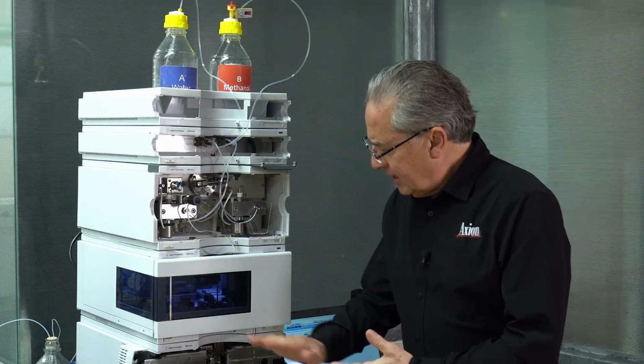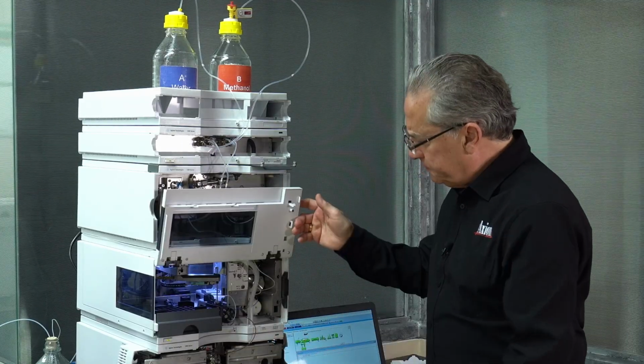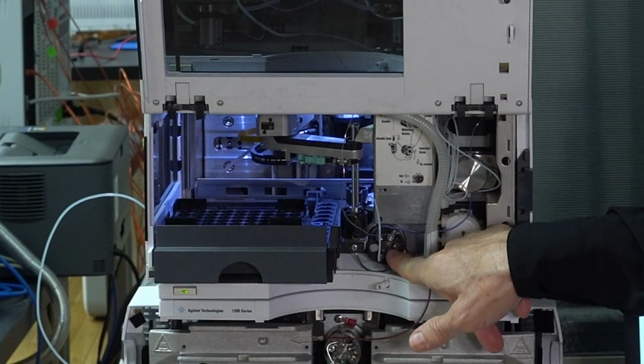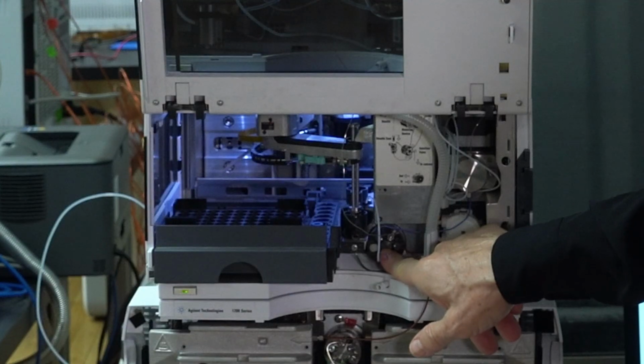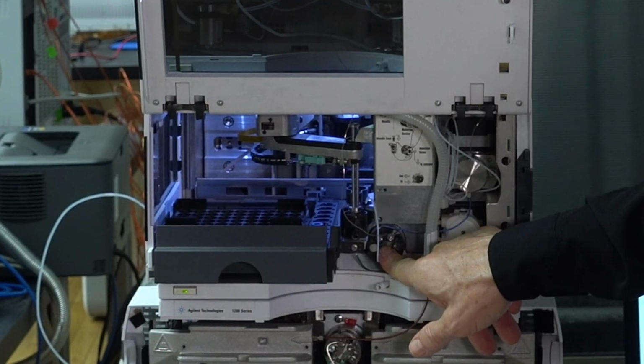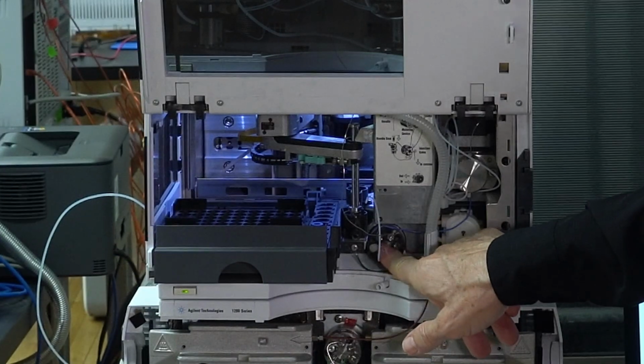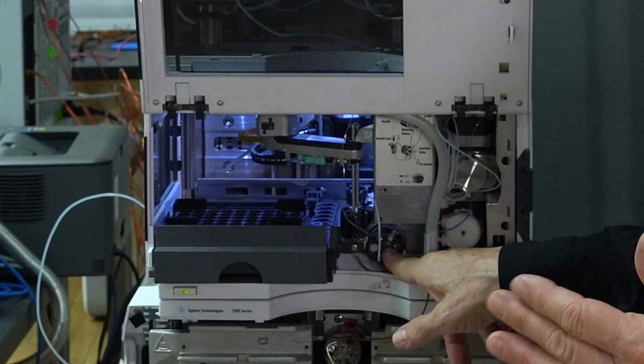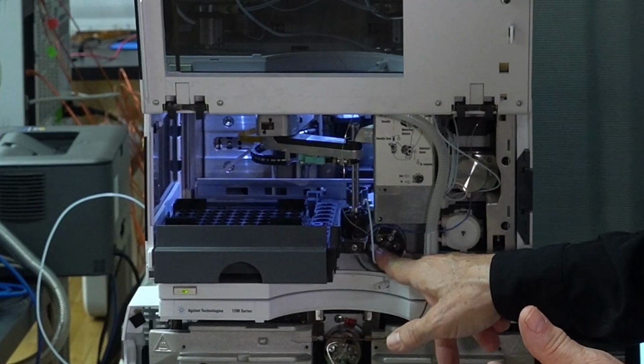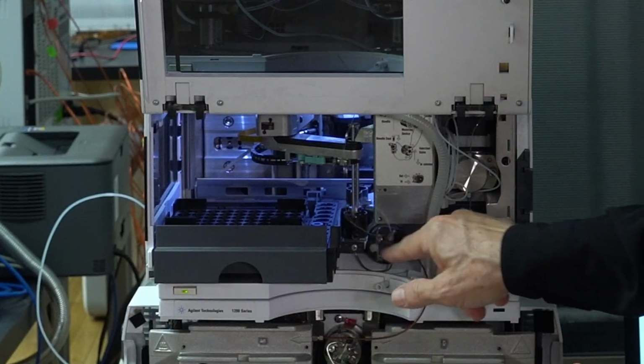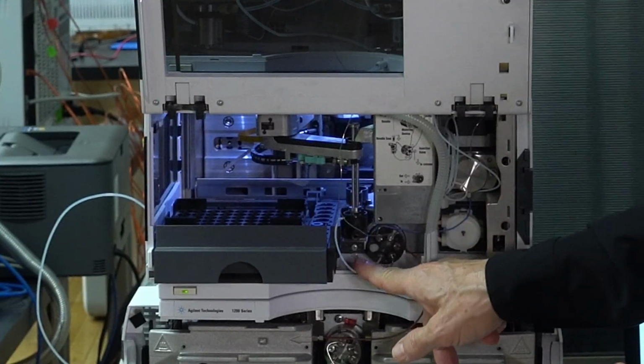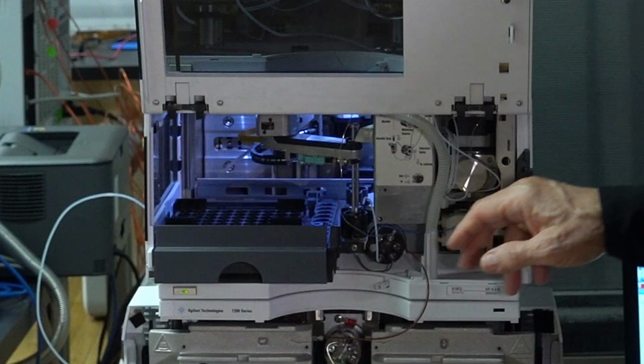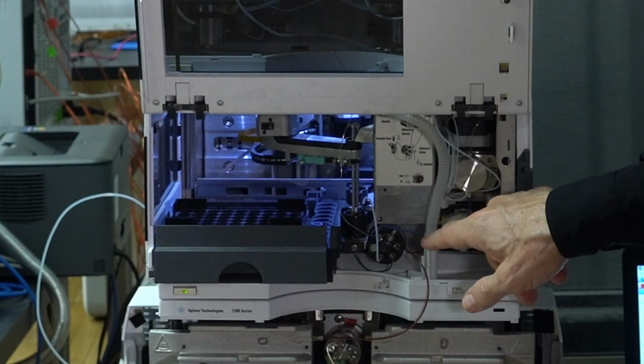And it's inside the autosampler itself, and it's inside the Rheodyne valve. The Rheodyne valve is what switches us from online to offline, or from main pass to bypass. It's what isolates the high pressure from the low pressure parts of the system. The way it works is it has 6 connecting pipes, and you see the 6 tubes going in. Boy, I'm always challenged to see if I can name all 6 of them.